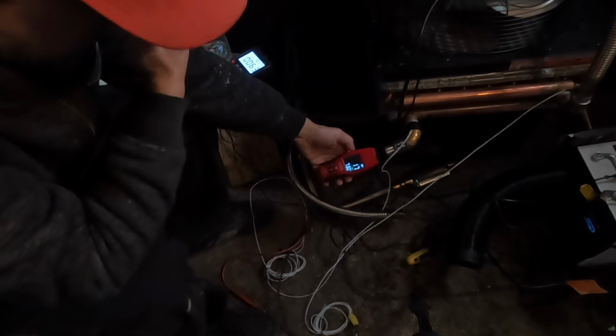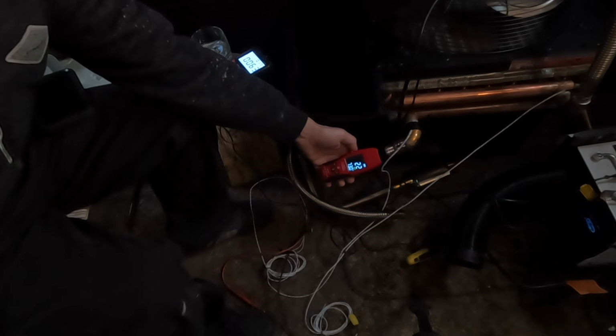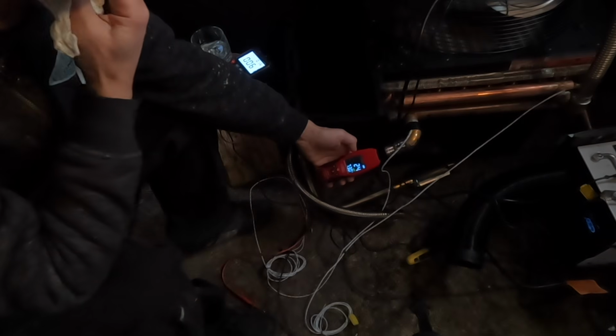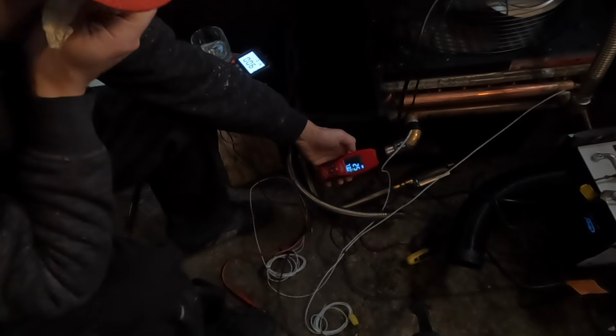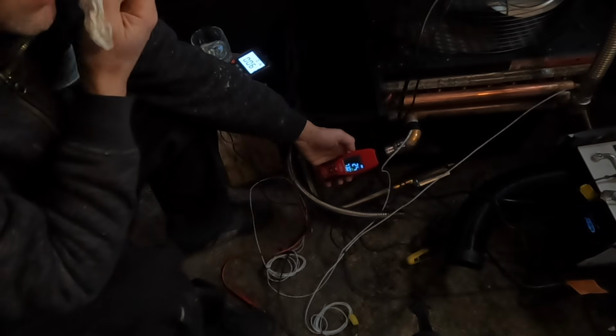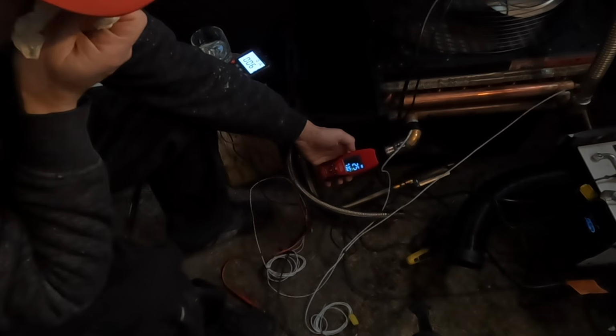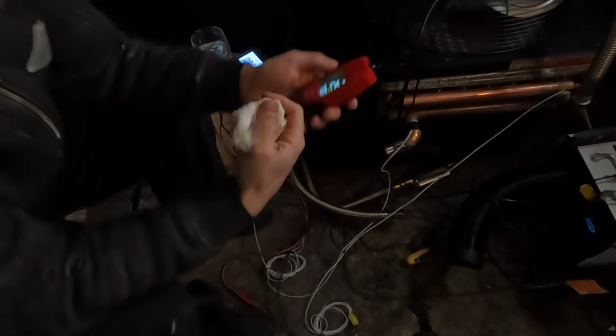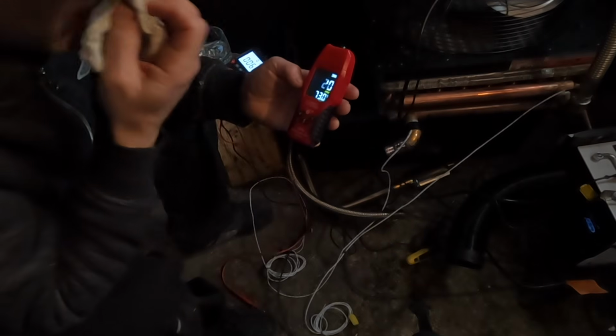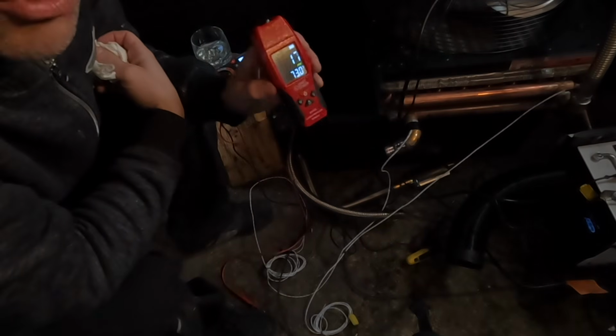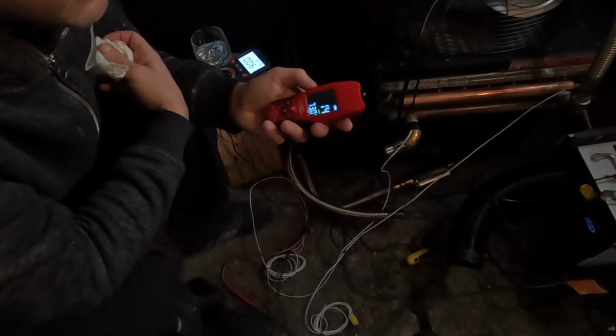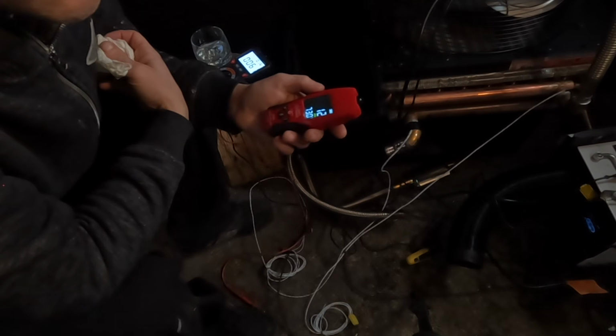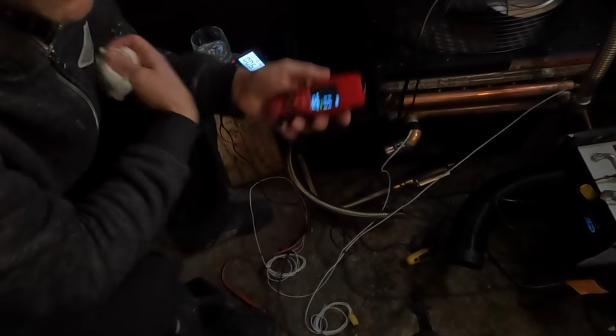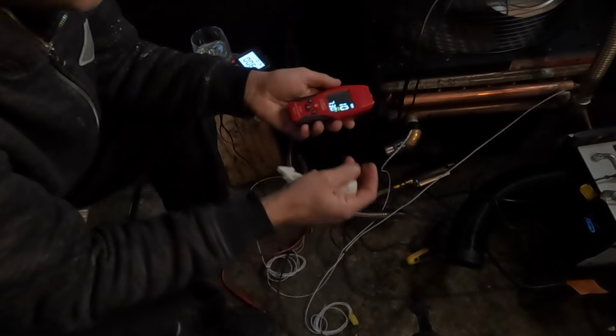We're jumping up fairly quickly. 22 parts per million. 25. Okay, so that's actually very reasonable. Between 24 and 26 parts per million is extremely reasonable. I'm not really concerned about that causing soot to build up inside the chamber.